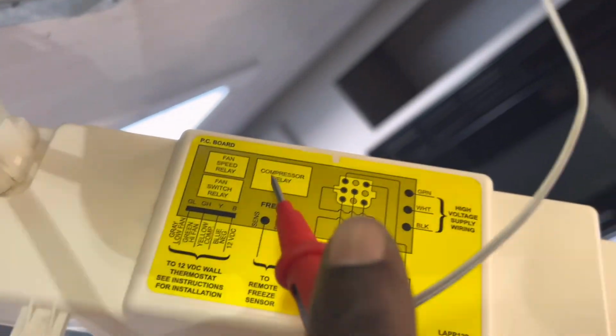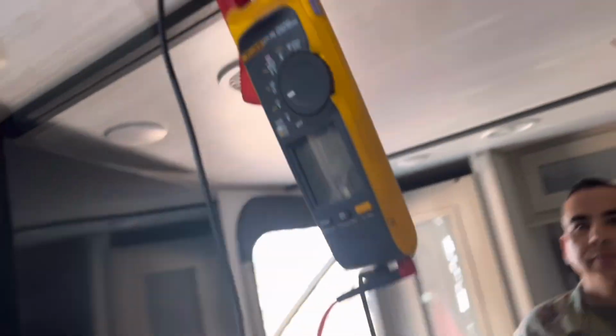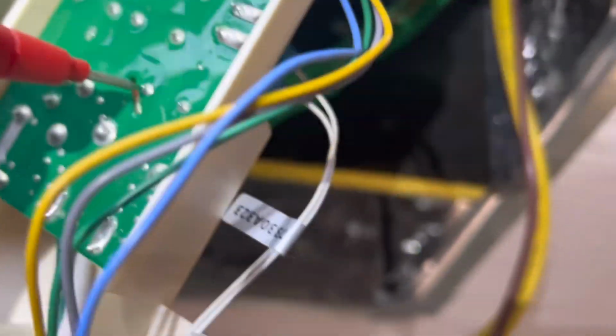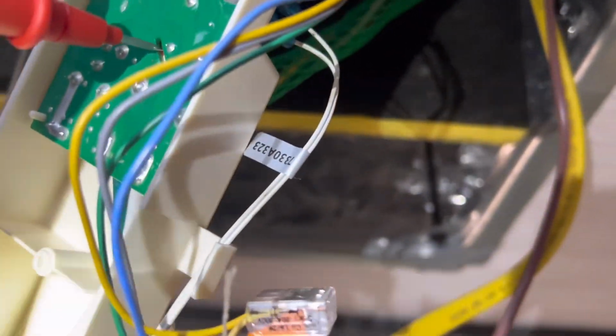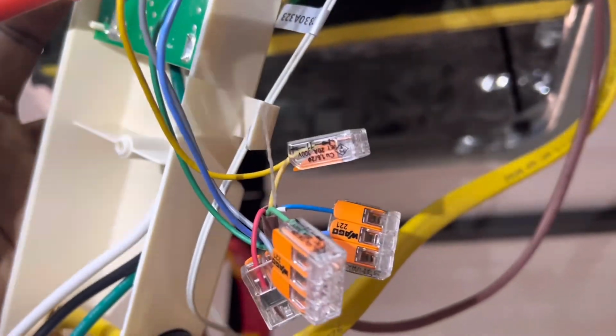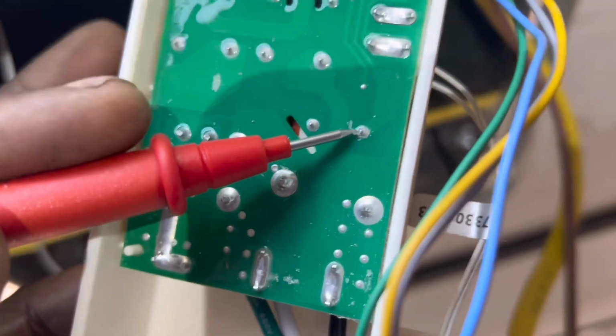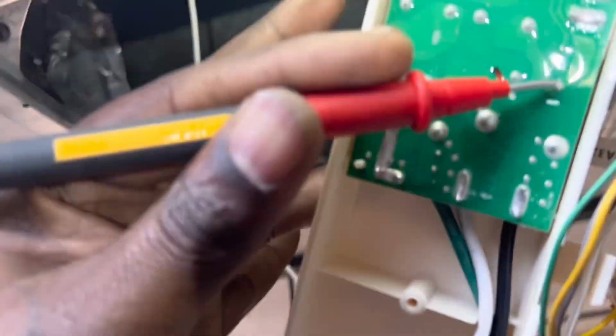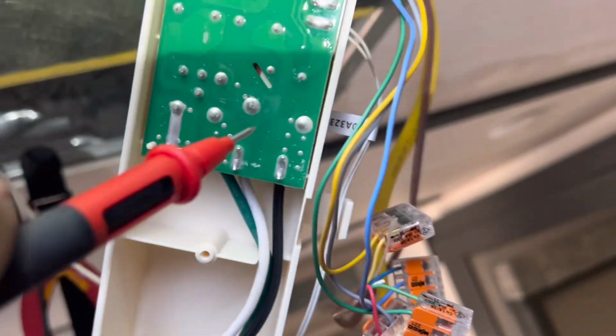the compressor relay. The compressor relay should have, if I check my control side on the board, my voltage of 13. So I'm checking the control side of that relay. I'm just doing it from the back of the circuit board. Okay, you can see I have my 13.7 volts. Okay, but it's supposed to engage an electromagnet which closes the 110 side, which are these two posts.